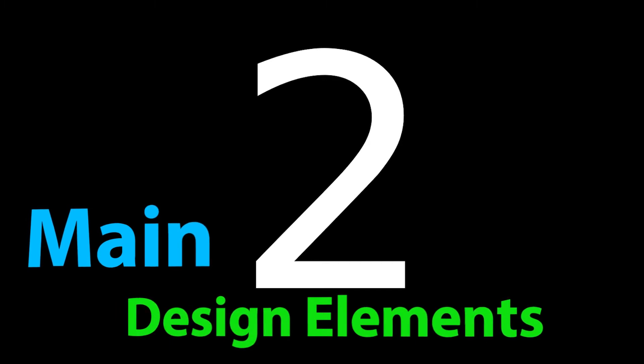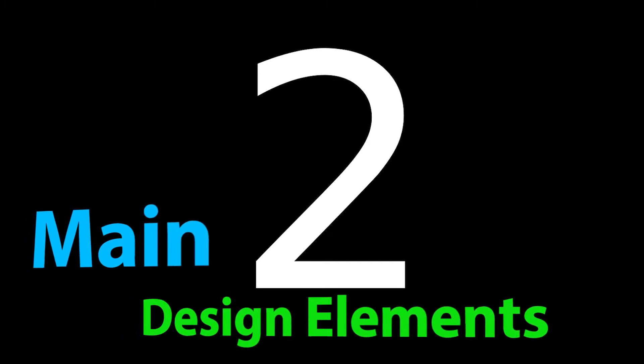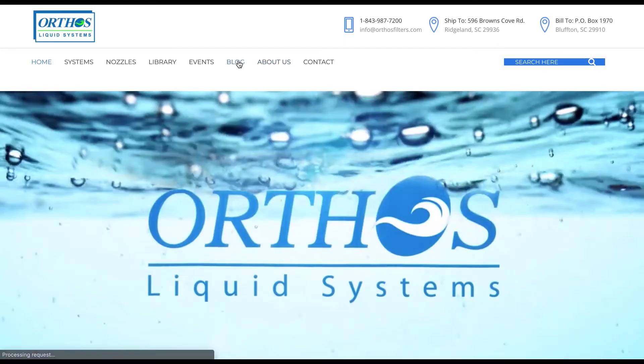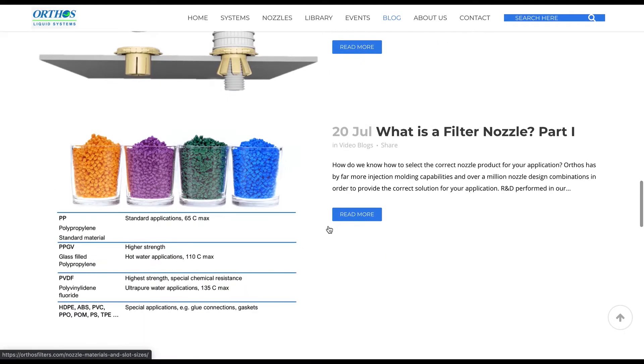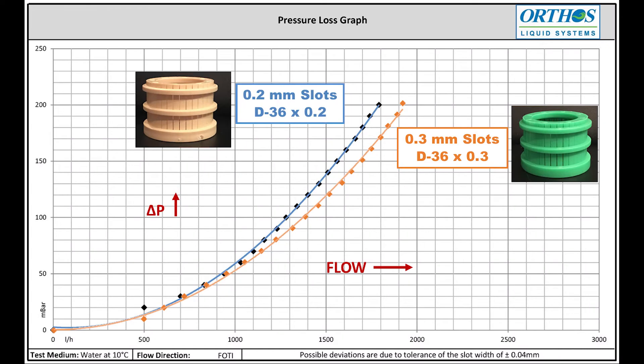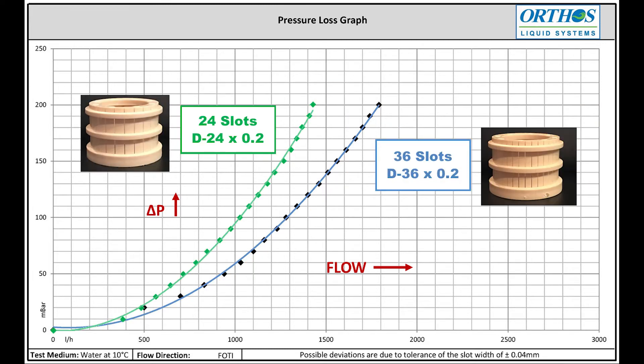There are two main design elements that determine pressure drop through a nozzle at a given flow rate. First is screen construction. Be sure to watch part one of this series in which I discuss screen slot width. A choice may be required between more than one appropriate width. For the same number of slots, smaller width slots impart more pressure drop than larger. Utilizing the same width slot, fewer slots in a screen will create more pressure drop at the same flow rate.